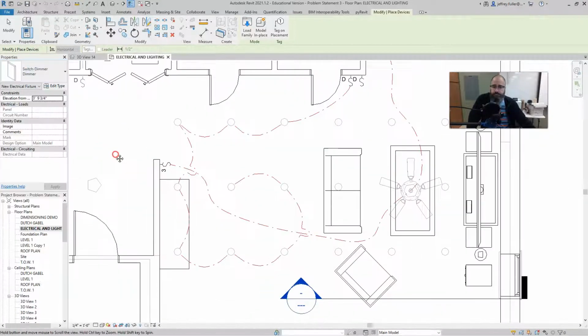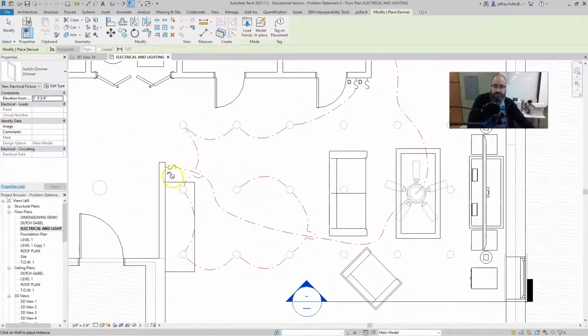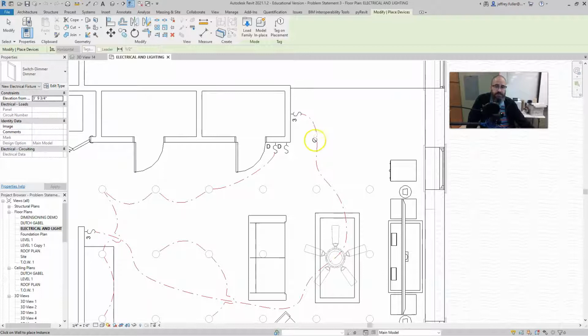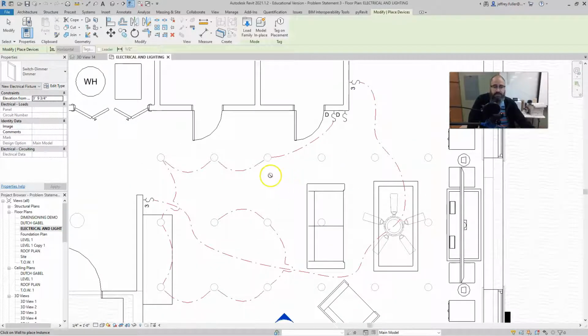So as you see, I've got a three-way switch, and if you remember correctly, a three-way switch is for controlling lighting from two different locations. Okay, so three-way switch here, and the wire from it travels along this path to the fixture that it controls, and then on to its next point of control. Okay, so that is again for the lighting fan.